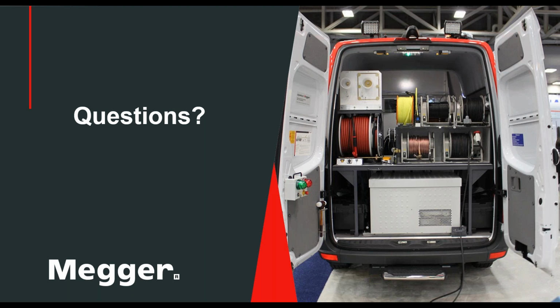If I have 50-50, then I can build an average velocity and use that. But always keep in mind, whenever you average or calculate velocities, depending on where the fault is actually located, it might have an impact on that distance.